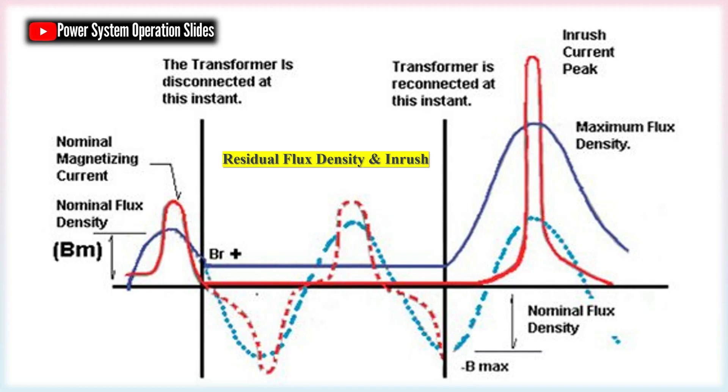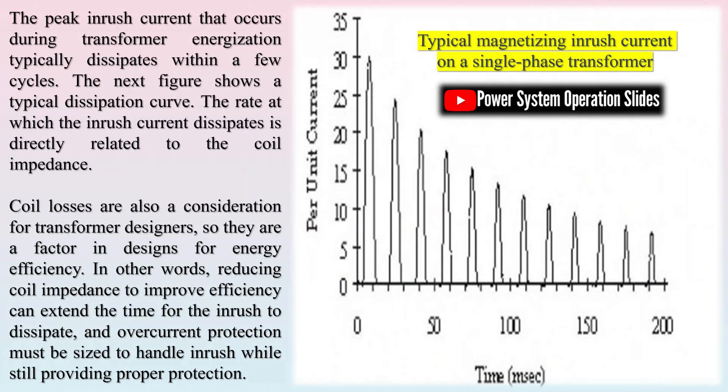Tripping of protective devices: If the inrush current is excessively high, it may cause circuit breakers or the transformer's fuses to trip. These protective devices are designed to detect and respond to abnormal current levels to protect the system from damage. In cases of severe inrush current, false tripping of protective devices may occur, resulting in unnecessary power interruptions. A fuse that accommodates the transformer's initial inrush current should be selected.